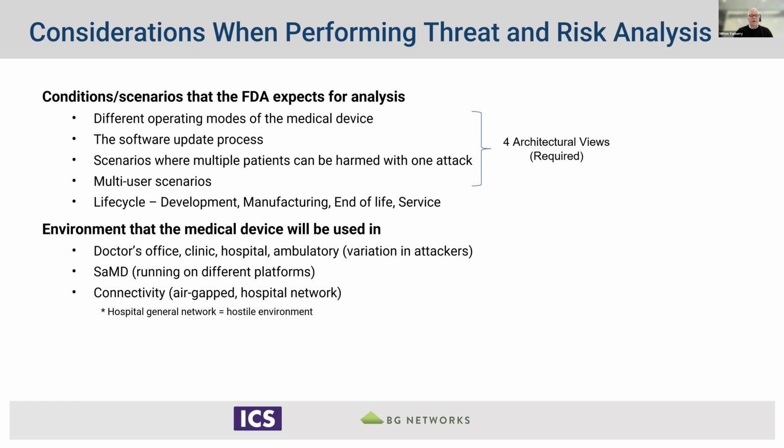And really what you're looking at here is a variation in the attackers across each of these environments. If your product is software as a medical device, that means that it could be running on different types of hardware and different types of operating systems. So that's another environmental consideration. And then, of course, maybe first and foremost would be just connectivity. Whether the device is, as I call it, air-gapped, meaning it has no network, or if it's on a hospital network, where generally speaking, I would say that a hospital network should be considered pretty much a hostile environment.